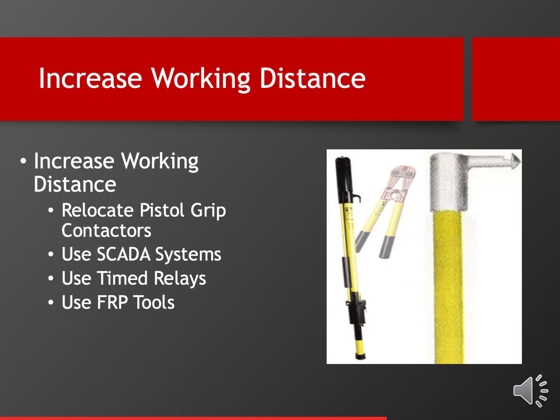Now, increasing working distance. There are several ways to do it. One of them is for those types of breakers that operate on a pistol grip contactor, on a panel cover, panel door, if you will. There's no law that says those things have to be right in front of the device that actuates. So if you have the choice of relocating those pistol grip contactors, even 4 or 5 feet away from where it is now, 20 feet would be better, that would give us additional protection. So if they reset a breaker or whatever and it blows up, having some distance between you and those arcing terminals is a great idea.